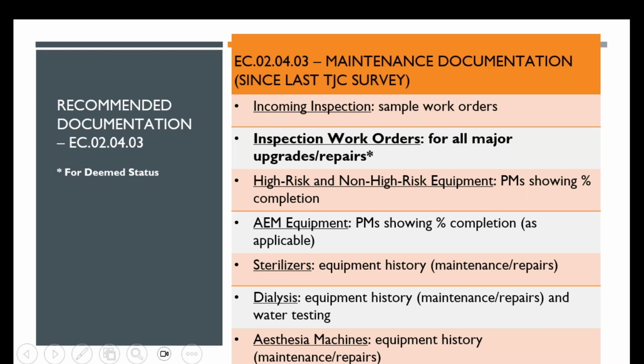And for high risk and non-high risk equipment and AEM, have PM work order counts and percent complete each month. If this has been a pain point for your facility or department in the past, having a narrative, if you don't meet 100%, why? It's really important because, like I think I was sharing glances with everybody earlier, getting the non-high risk completion rate to 100% is hard. And finally, for dialysis water, have maintenance records and water testing results and any action items for when colony counts are out of range and how you remediated this, which probably will come from your dialysis department.